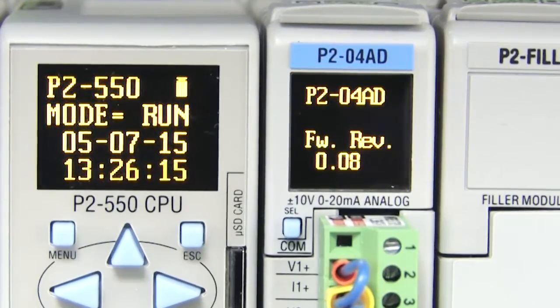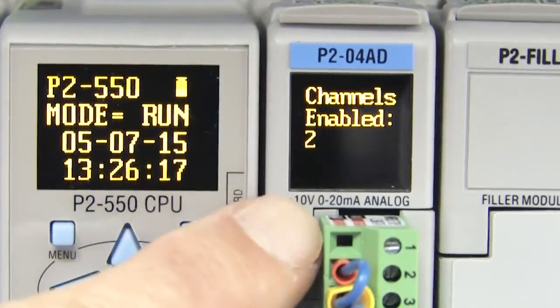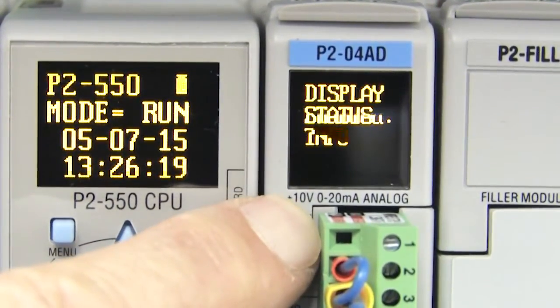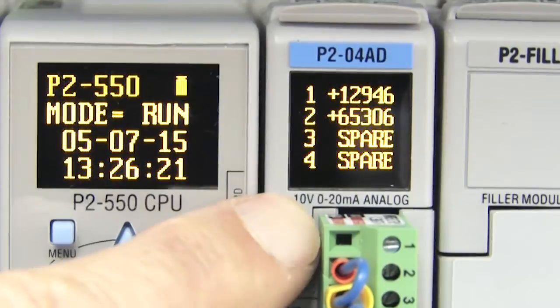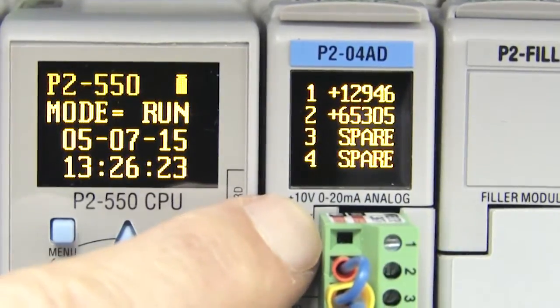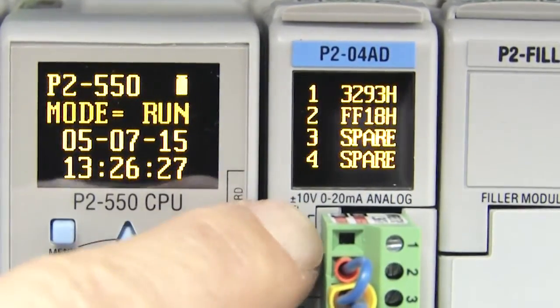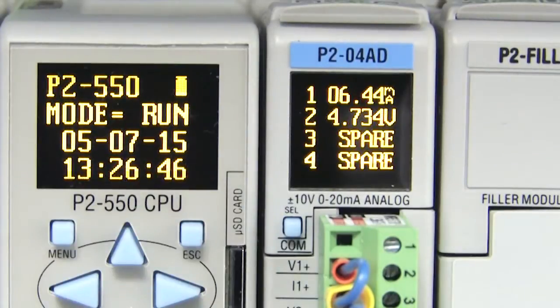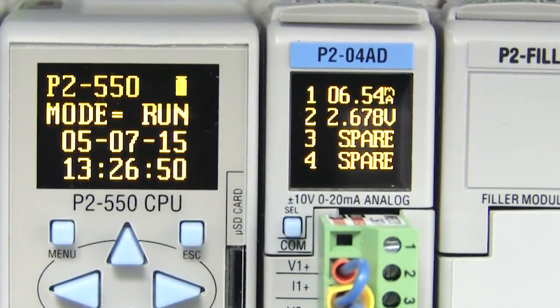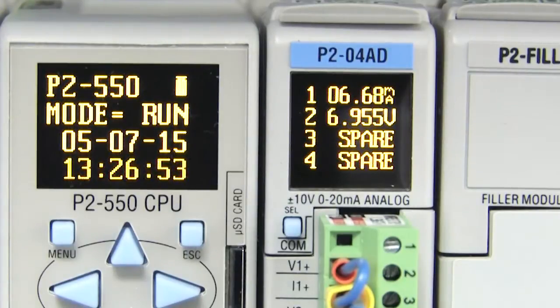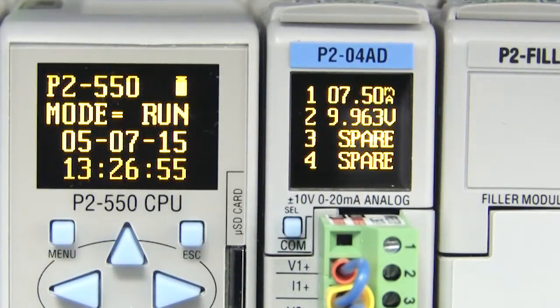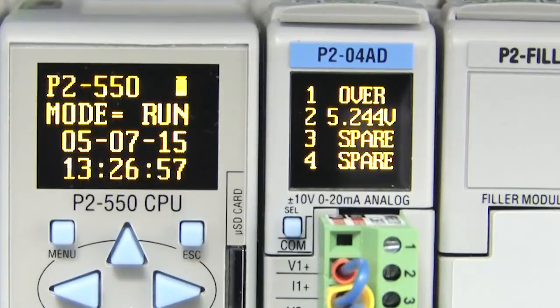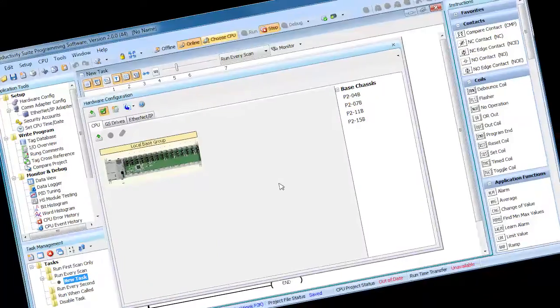And of course the analog values are displayed right on this analog module screen. You can even select how you want those results displayed – raw values, hexadecimal and current or voltage. This OLED display makes debugging analog inputs easy because you can see the answer right on the module and immediately know if the problem is outside or inside the controller. I love that.